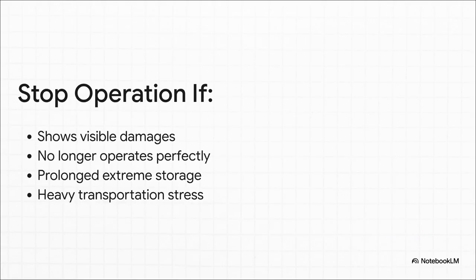So what exactly constitutes unsafe operation? Well, here are the specific conditions. If there are visible damages, obviously. If the software or hardware no longer operates perfectly. And frankly, the manual philosophically admits that no software is ever completely error-free, so you have to be vigilant. You also have to stop if it's been stored in extreme temperatures, high humidity, or corrosive environments for a prolonged time, or if it took a major beating during transport. Exceptional stress on the outside means untrustworthy measurements on the inside.